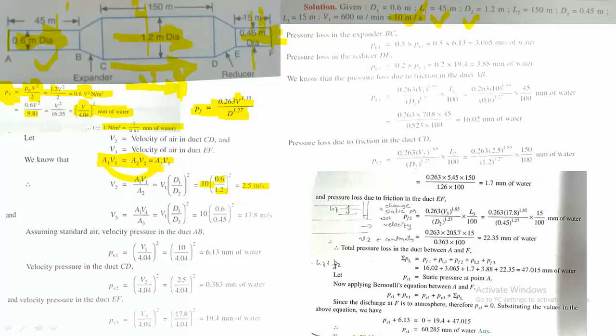Similarly, using A1V1 = A3V3, we get V3 = V1 × (D1/D3)². V1 is 10, D1 is 0.6, D3 is 0.45. The velocity in EF section becomes 17.8 meters per second. Velocity calculations for all sections are now complete.